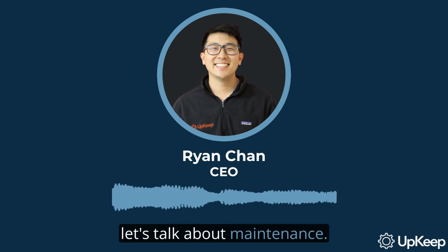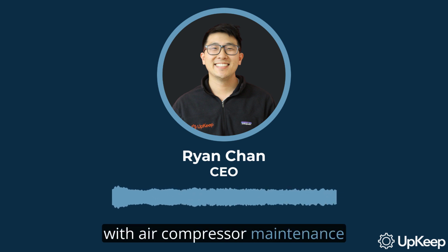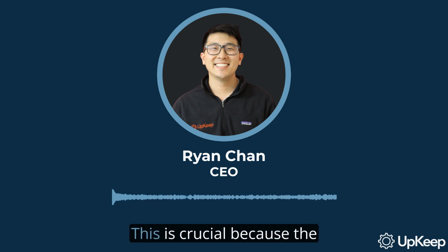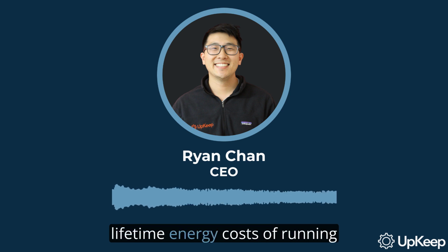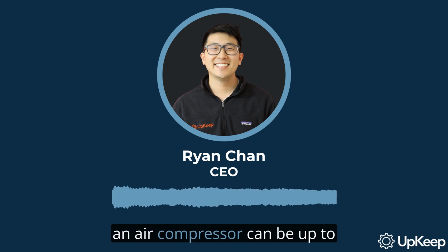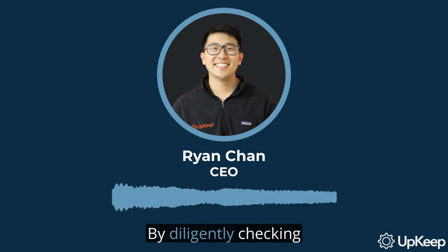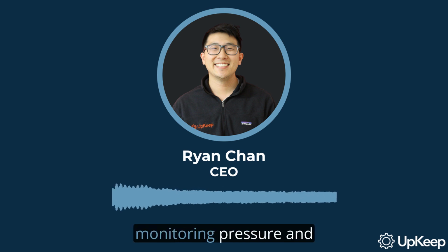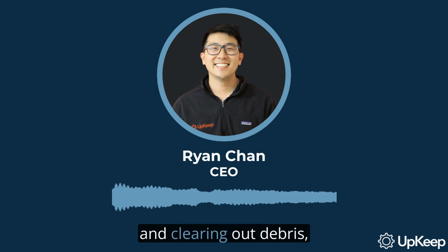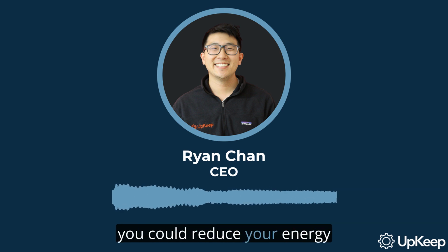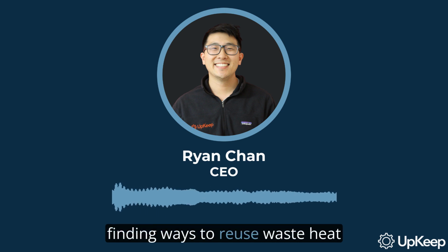Now let's talk about maintenance. A lot of the tasks associated with air compressor maintenance focus on conserving energy. This is crucial because the lifetime energy costs of running an air compressor can be up to 20 times the initial purchase price. By diligently checking for leaks, monitoring pressure and temperature variances, and clearing out debris, you could reduce your energy bills by a third. Additionally, finding ways to reuse waste heat can further cut down on energy costs.